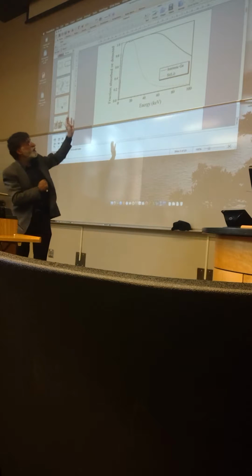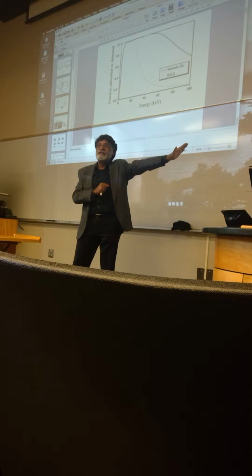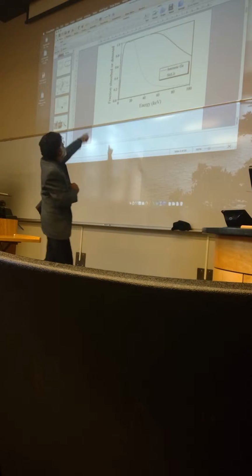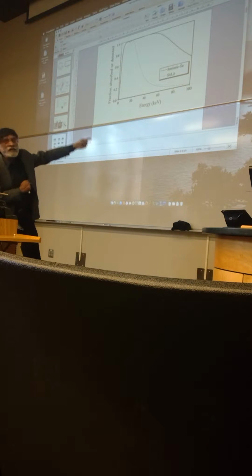The beryllium window is solid, but it absorbs all the low atomic number elements below, let us say, atomic number 10. So that's why the efficiency for the low energy drops off. So on the one side you have the window issues. On the other side, the X-ray just goes through undetected. So the efficiency drops at one end because of the window, and at the other end because of the X-ray going through undetected.